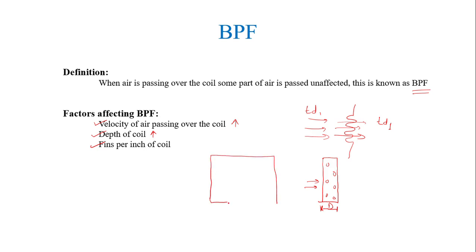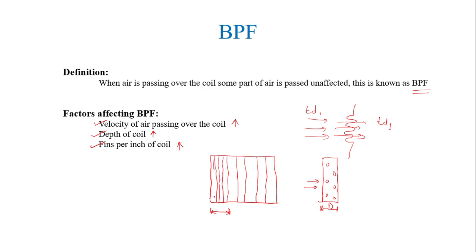The third factor is fins per inch. In the front view of the coil, fins are provided to increase the surface area for better heat transfer. In one inch length, the number of fins present is the fins per inch. If fins per inch are less, there will be more gap between two fins and air can easily pass unaffected. If you increase the number of fins, the gap decreases, more air is affected, and hence the bypass factor will be less.